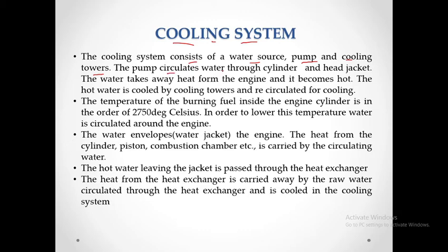Here the pump circulates water through the cylinder and head jacket. The water takes away heat from the engine and becomes hot. The hot water is cooled by the cooling towers and recirculated for cooling. The temperature of the burning fuel in the engine cylinder is about 2750 degrees Celsius. With this much temperature inside, cooling is very necessary.